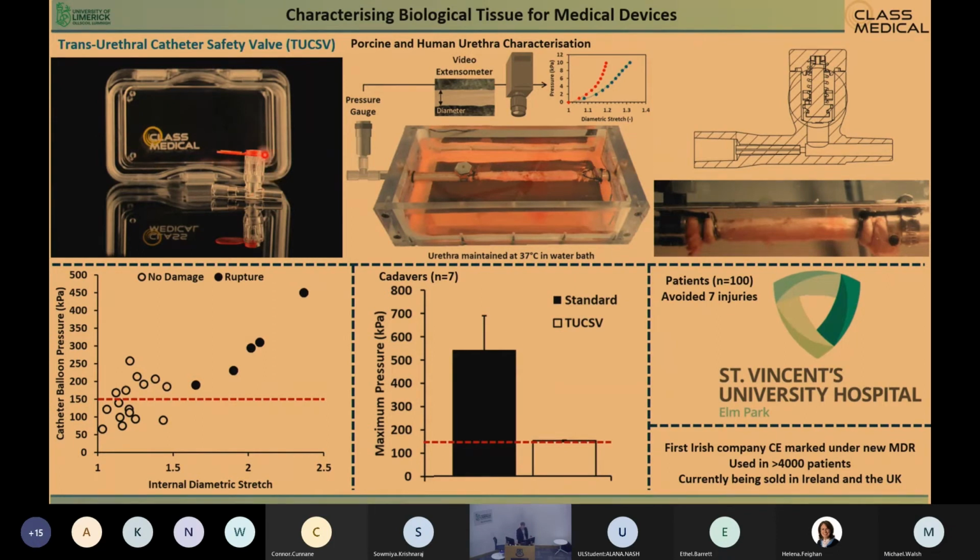It's just basically a pressure release valve with a flow restrictor, and the intention here is that the pressure release valve will trigger at the point before tissue injury can occur. So you'll see it in cross section here. Here is the valve, here is the restriction. But at what pressure do we want the valve to actuate to prevent damage?